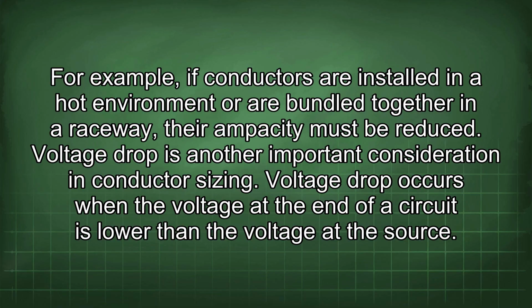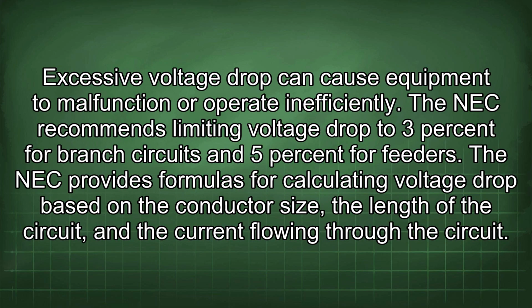Voltage drop is another important consideration in conductor sizing. Voltage drop occurs when the voltage at the end of a circuit is lower than the voltage at the source. Excessive voltage drop can cause equipment to malfunction or operate inefficiently. The NEC recommends limiting voltage drop to 3% for branch circuits and 5% for feeders. The NEC provides formulas for calculating voltage drop based on the conductor size, the length of the circuit, and the current flowing through the circuit.